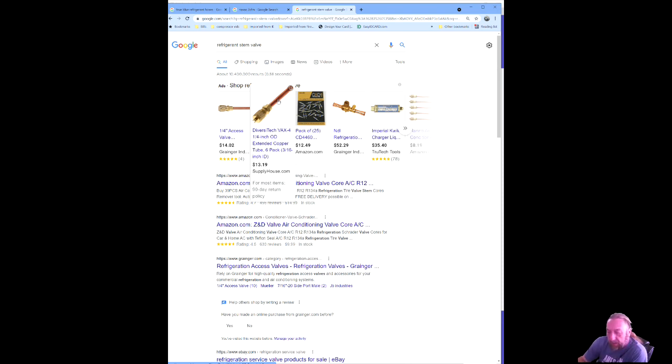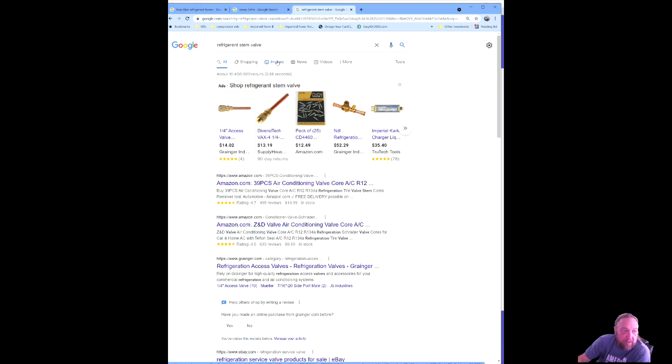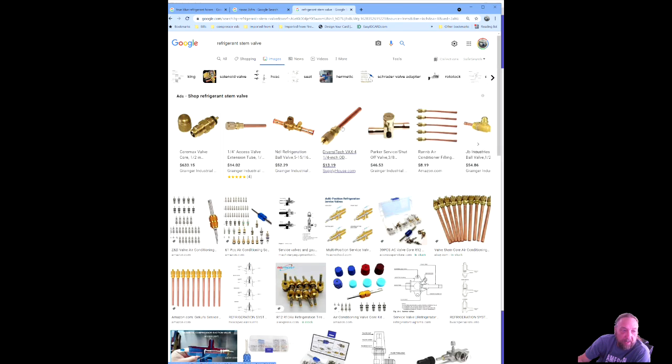Remember, in refrigerators we're only talking about 3 or 4 ounces of refrigerant in liquid form, maybe 5 or 6 on some of the bigger ones. Having the bigger hose really isn't going to make a huge difference. Maybe you feel like it's going that way, but after it comes out, it's going to drop into a deep vacuum, but inside your system is not going to evacuate as fast as the other side. Because if I took this valve here, let me just see if I can get an image and give you an idea what I'm talking about.